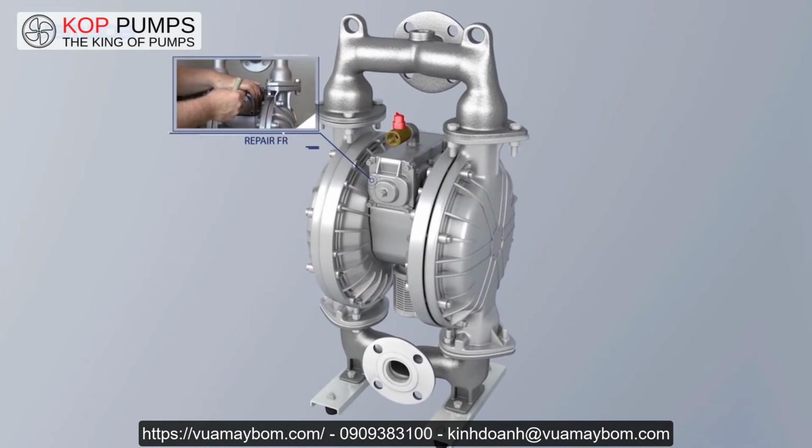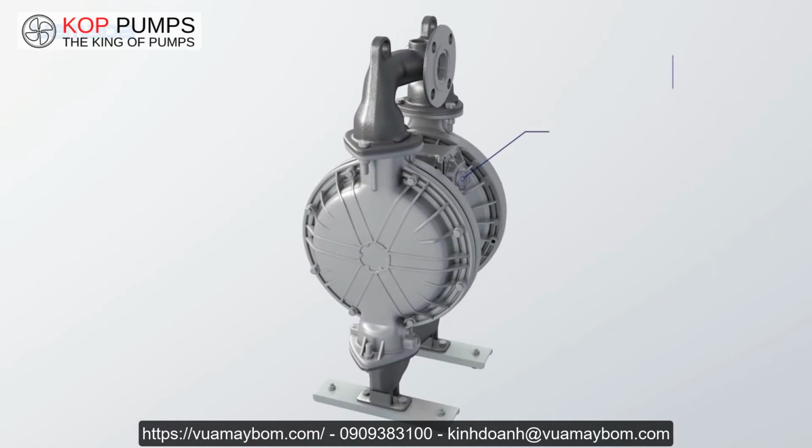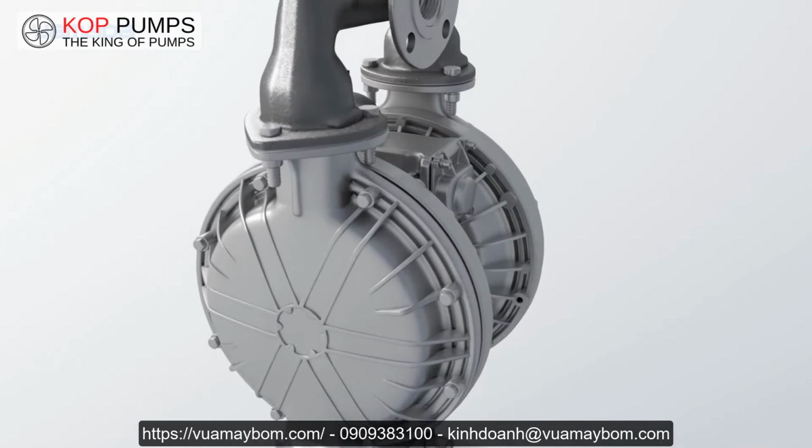Our air valve is outside accessible for easy inspection and is completely repair friendly. Yamada air valves have the longest service life in the industry due to their lube-free design. The non-lubrication design is important because one of two things can happen when lubrication is needed. One, lubrication can be washed away by the moisture in the air, causing wearing issues. And two, moisture and particulate can coagulate and create a sandpaper effect, hence causing more wearing issues.